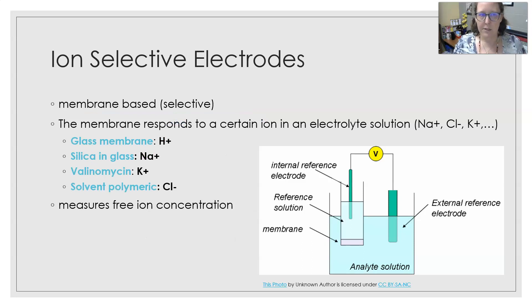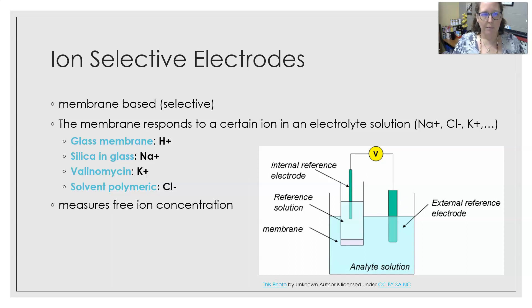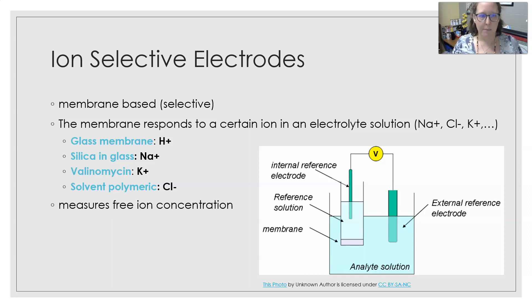One of the applications is ion selective electrodes. These are used all across clinical chemistry in the large analyzers. They are membrane-based, and that is what makes them selective. The membrane responds to a certain ion in an electrolyte solution — those ions can be sodium, chloride, potassium, etc. The glass membrane and the makeup of the glass can vary.